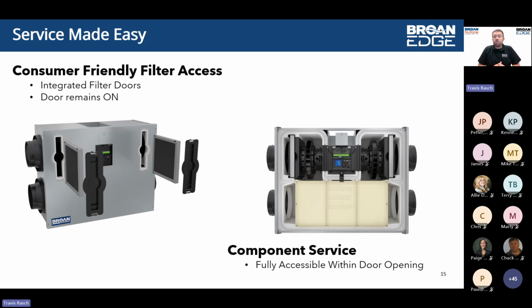Sabina has a question. Does the service door swing open or pull off? Great question, Sabina. It simply pulls off. So you remove those fasteners that I mentioned before, and basically there are flanges all the way around the interior perimeter of the door. You can use that flange and basically just pull it directly off. Behind that steel door panel is the insulation panel. That just sits inside the perimeter of the housing. You carefully pull that off, and then you can get to exactly what I'm showing here on the lower right screen in this rendering. So that's basically what you would see once you pull that door off directly. Hopefully that answers your question, Sabina.